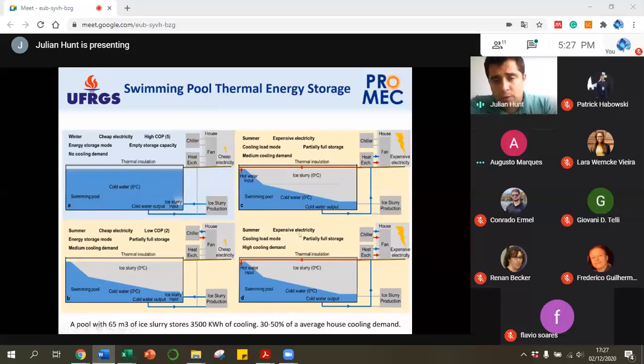Another approach: if electricity is expensive but you have very high demand for cooling, you also have to turn on the chiller. But that's life, sometimes it doesn't make sense otherwise. This is a base load cooling solution, not for peak demand. Peak is handled by air conditioning, which cools down immediately.